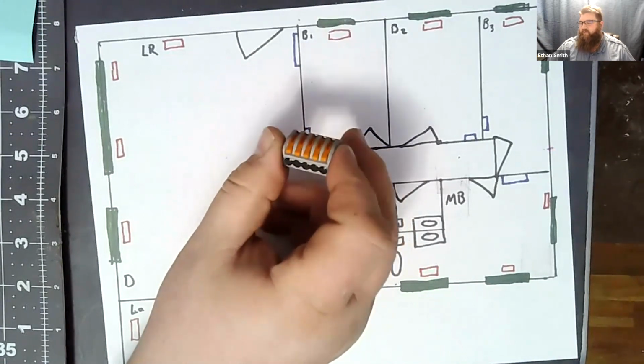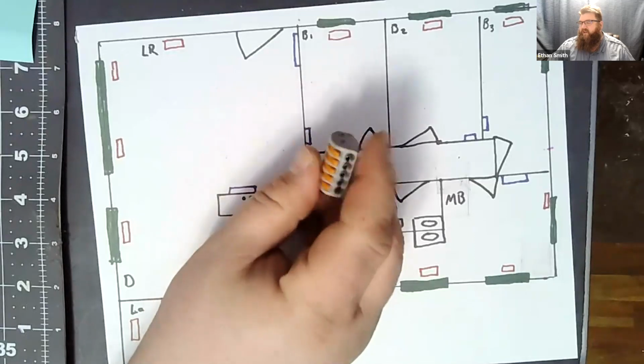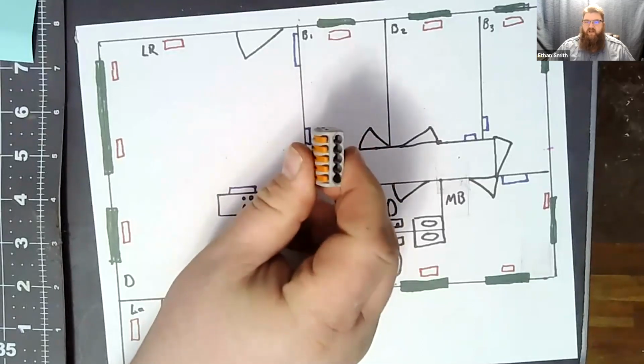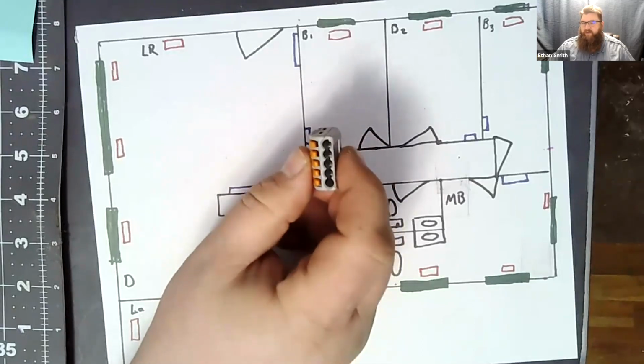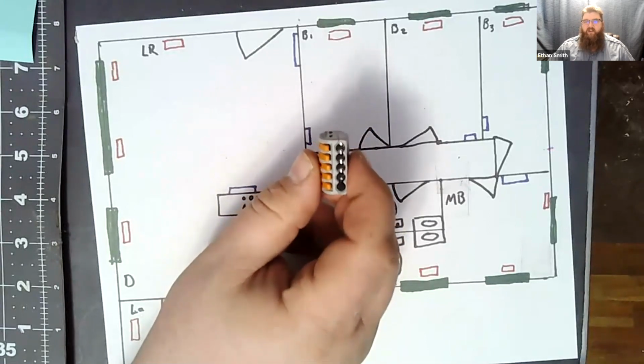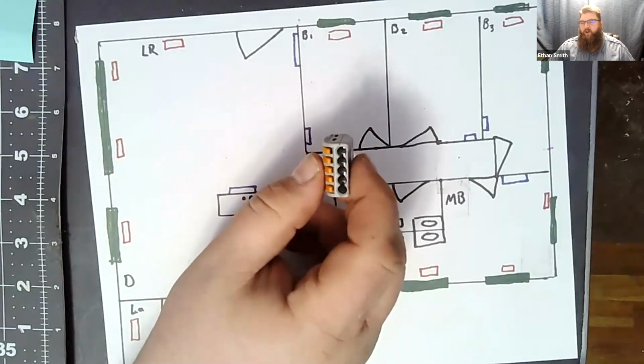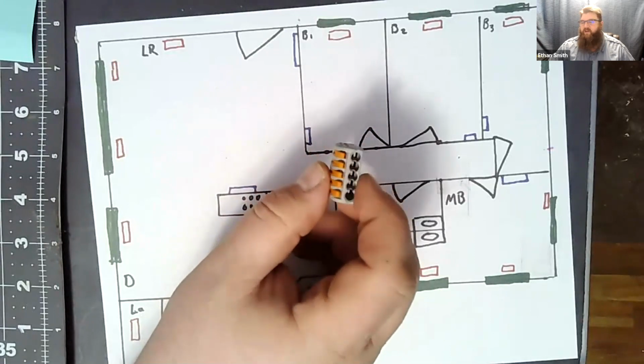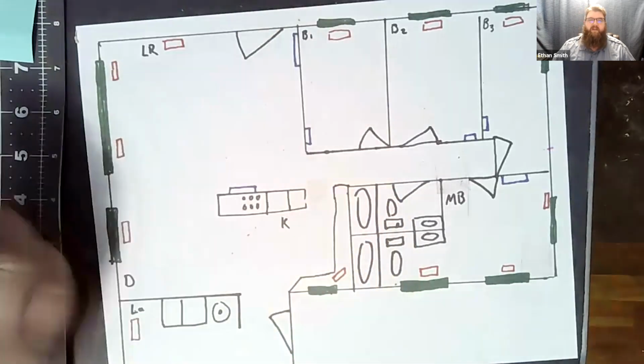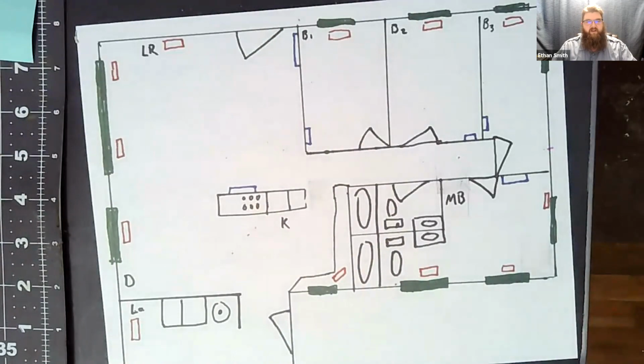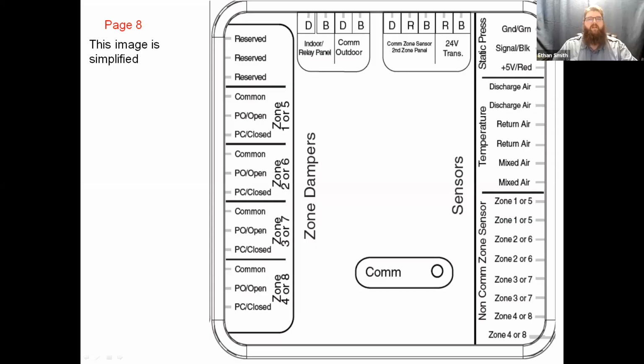So you can run a pigtail from the wiring terminal up to this and then get up to 4 more connections with this. The reason we like these is they put a nice positive clamp on each wire. You're not trying to shove them all into a wire nut and hope you get a good connection, especially when we're dealing with data transmission. All right, so there'll be 3 of those in your box that come along with the zoning system. Okay, so those are going to connect there.